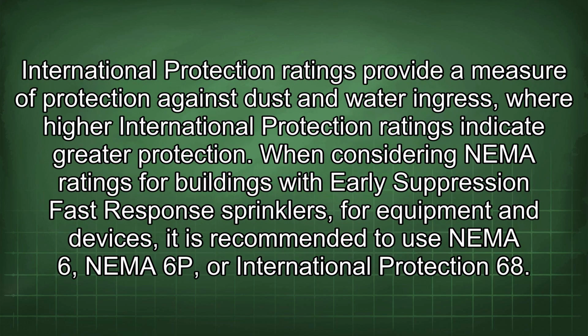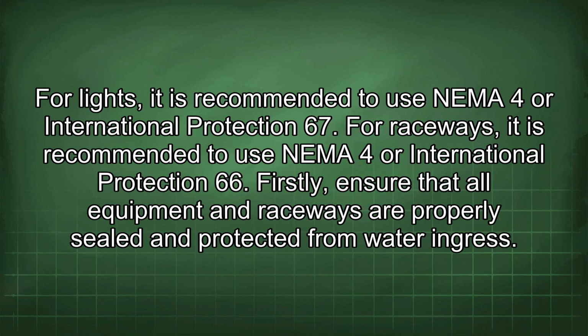International protection ratings provide a measure of protection against dust and water ingress, where higher international protection ratings indicate greater protection. When considering NEMA ratings for buildings with early suppression fast response sprinklers for equipment and devices, it is recommended to use NEMA 6, NEMA 6P, or International Protection 68. For lights, it is recommended to use NEMA 4 or International Protection 67. For raceways, it is recommended to use NEMA 4 or International Protection 66.